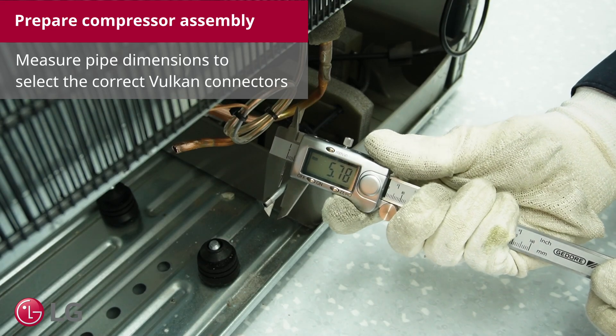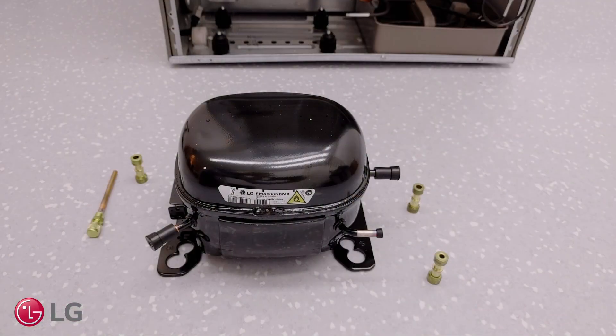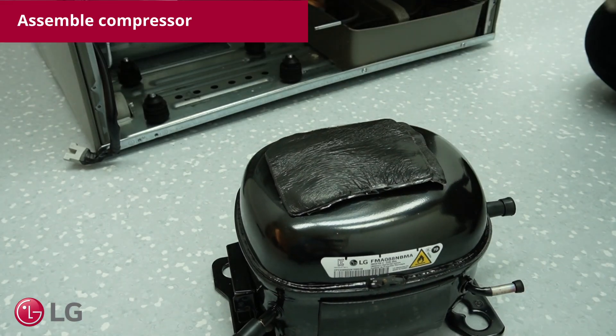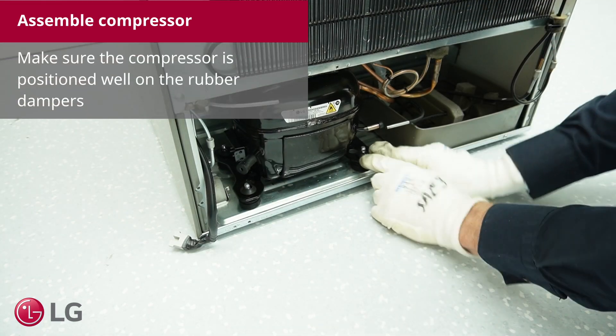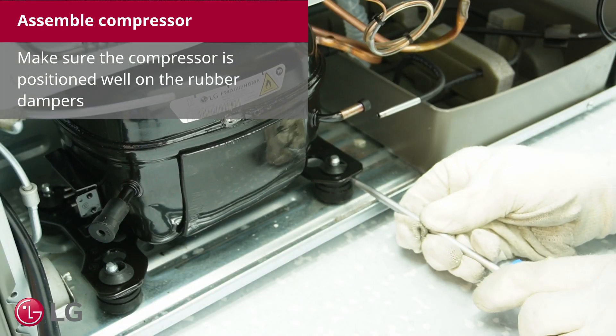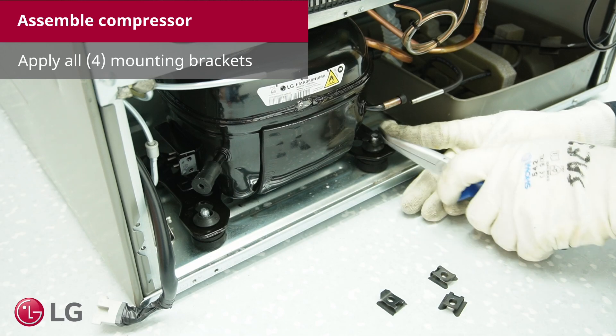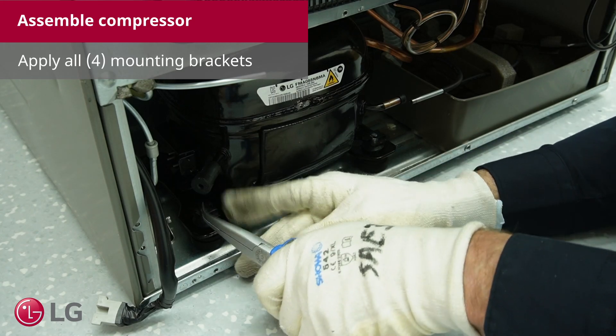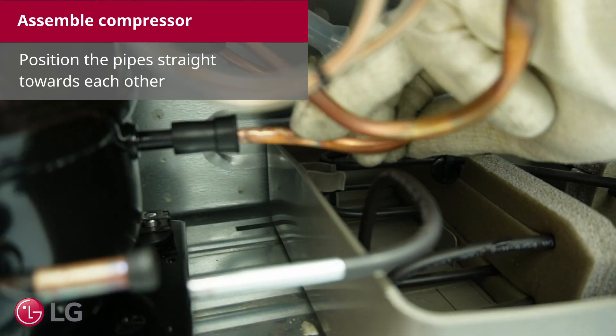Measure the pipe dimensions to select the correct Vulkan connectors. Reuse the damper from the old compressor. Make sure the compressor is positioned well on the rubber dampers. Apply all the mounting brackets. Leave the rubber caps on as long as possible to prevent air and moisture from entering.